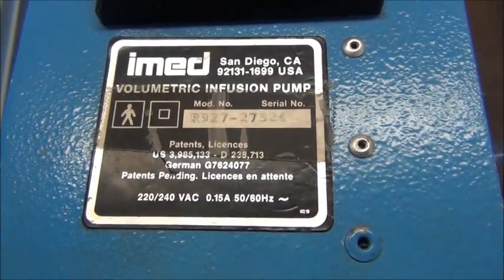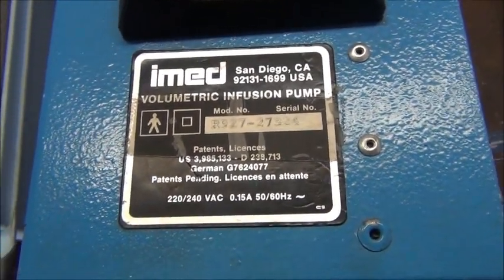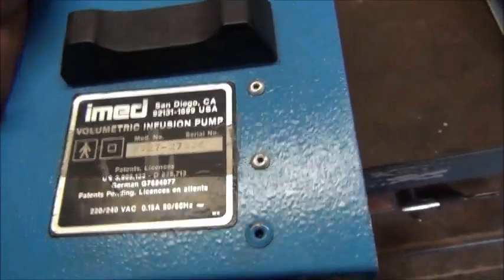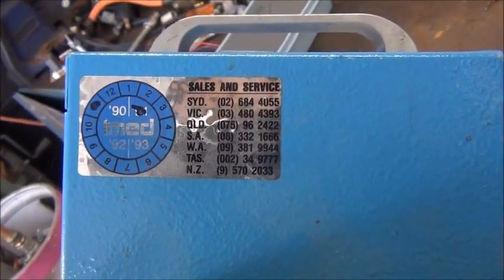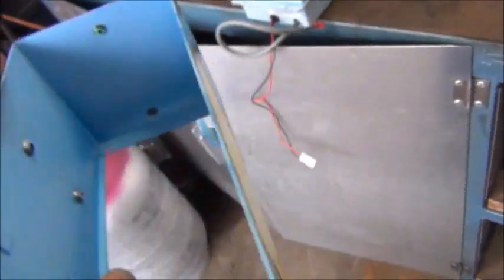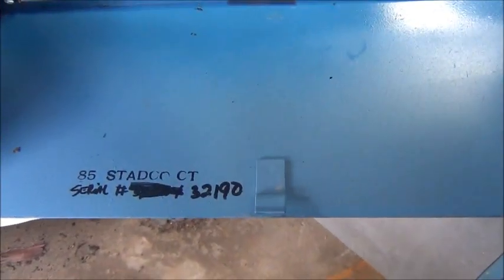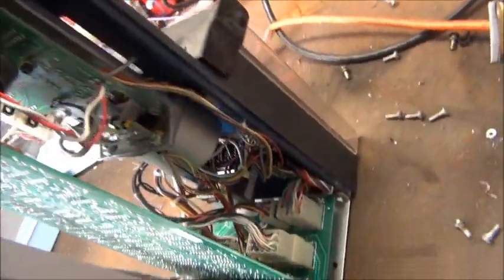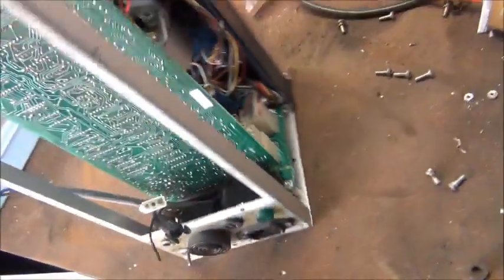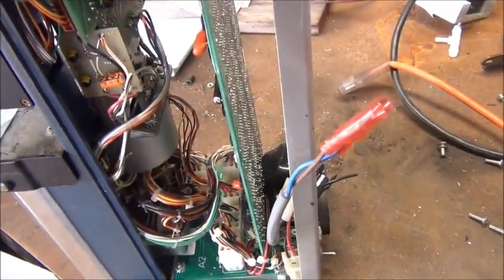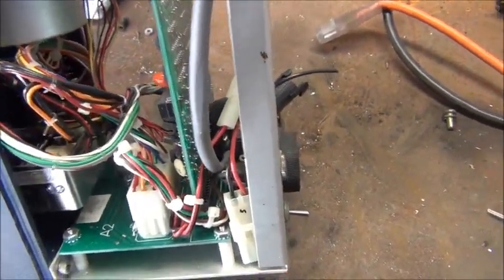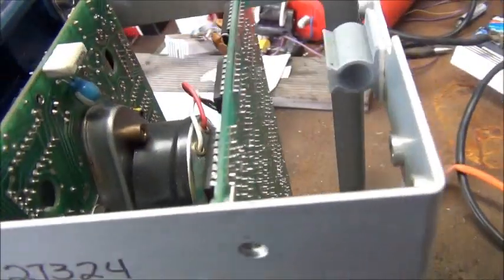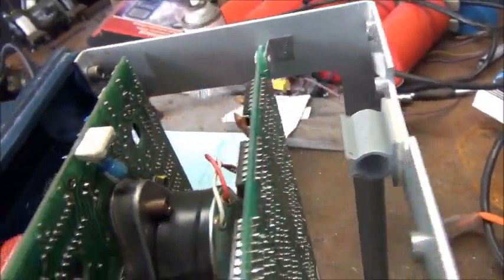Just a quick shot of the manufacturer's plate there for you. iMed, San Diego, California, USA. And obviously they have service agents here in Australia, and New Zealand. Very good. Interesting. Anyway, something I like about medical and military and communications gear is it's very well made. This machine is designed to not have any single point of failure, which would leave you with a non-functioning unit.